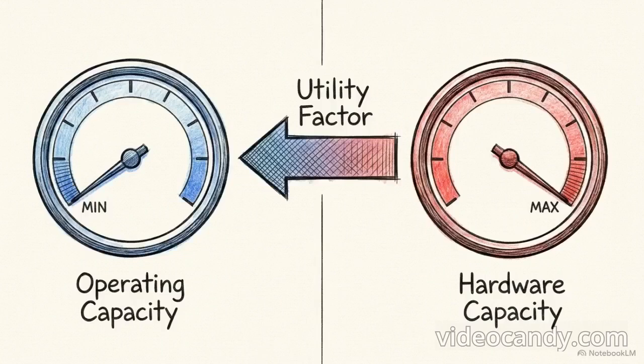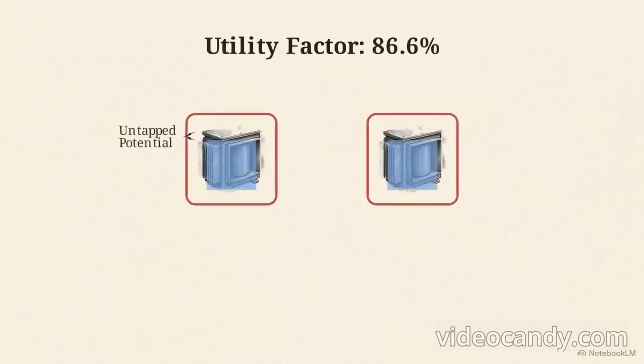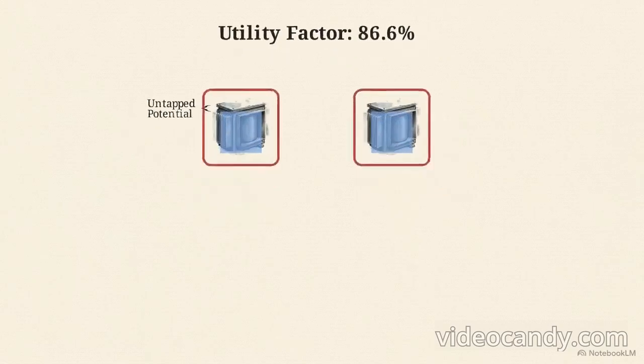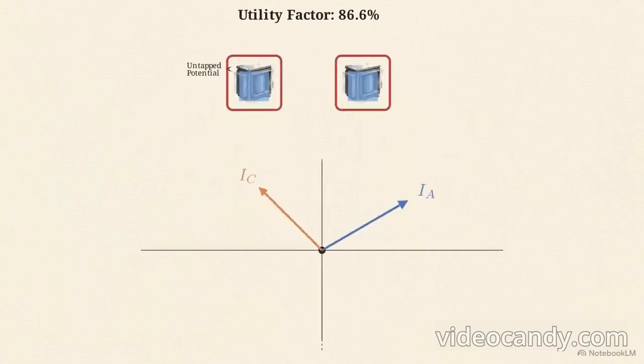An open delta bank actually operates at exactly 57.7% of the original closed delta rating. Power engineers measure this inefficiency using the utility factor, which compares the actual operating capacity to the available physical capacity of the hardware. The open delta has a utility factor of 0.866. That means even the 2 functioning transformers are not being fully utilized.